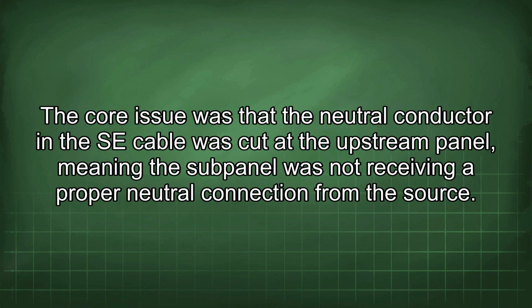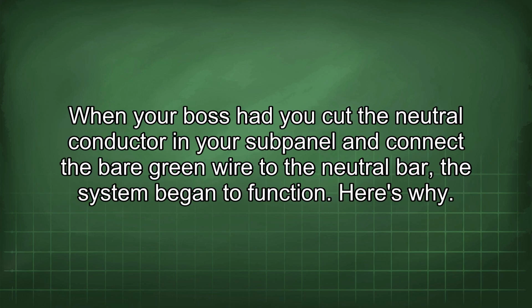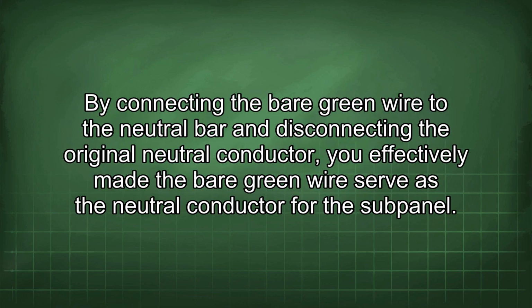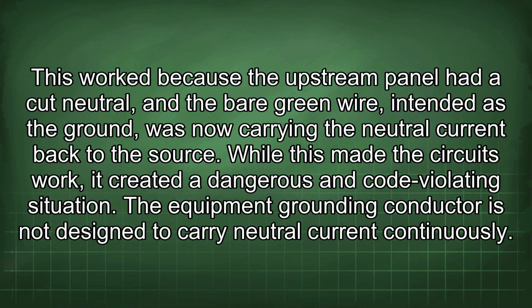The core issue was that the neutral conductor in the SE cable was cut at the upstream panel, meaning the subpanel was not receiving a proper neutral connection from the source. When your boss had you cut the neutral conductor in your subpanel and connect the bare green wire to the neutral bar, the system began to function. Here's why. By connecting the bare green wire to the neutral bar and disconnecting the original neutral conductor, you effectively made the bare green wire serve as the neutral conductor for the subpanel. This worked because the upstream panel had a cut neutral, and the bare green wire, intended as the ground, was now carrying the neutral current back to the source.